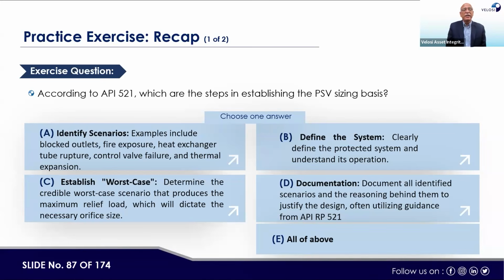Number 1, identify scenario. B, define the system: clearly define the protected system and understand its operation. Then C, establish worst case: determine the credible worst case scenario that produces the maximum relief load, which will dictate the necessary orifice size. Then D, documentation: document all identified scenarios and the resulting reasoning behind them to justify the design, often utilizing guidance from API 521.